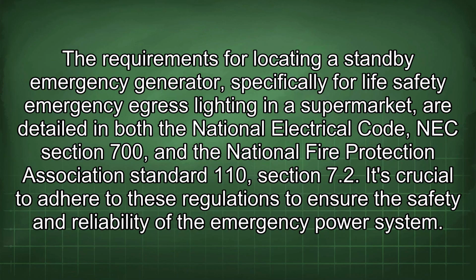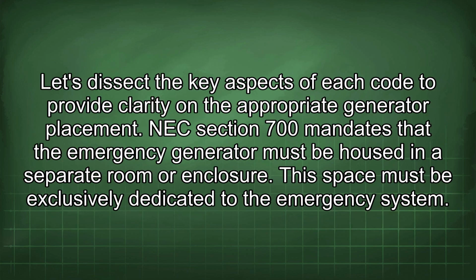The requirements for locating a standby emergency generator, specifically for life safety emergency egress lighting in a supermarket, are detailed in both the National Electrical Code (NEC) Section 700 and the National Fire Protection Association Standard 110 Section 7.2. It's crucial to adhere to these regulations to ensure the safety and reliability of the emergency power system. Let's dissect the key aspects of each code to provide clarity on the appropriate generator placement.